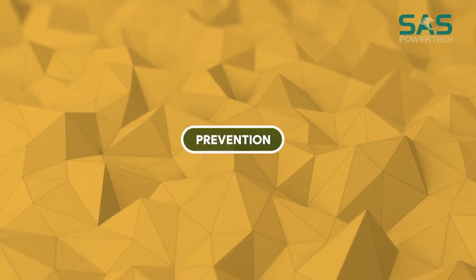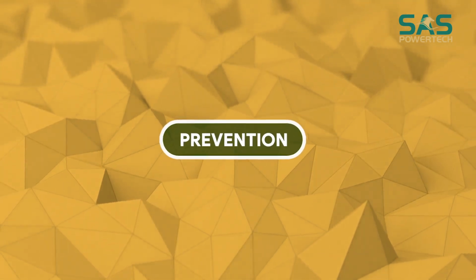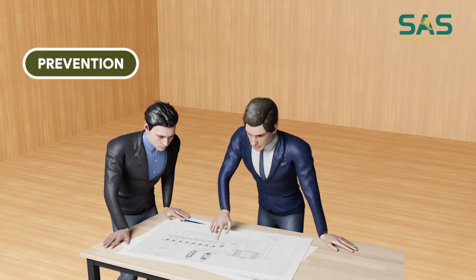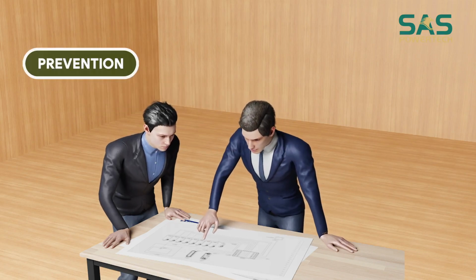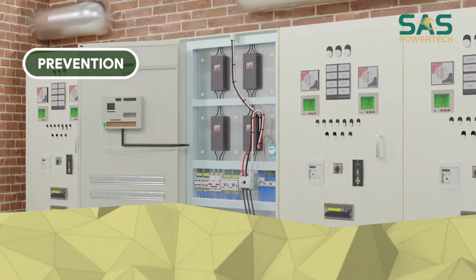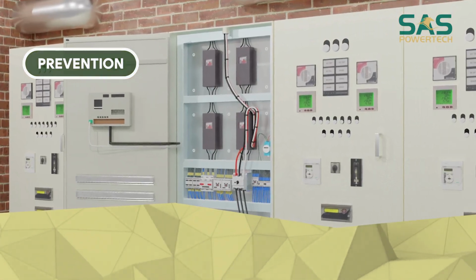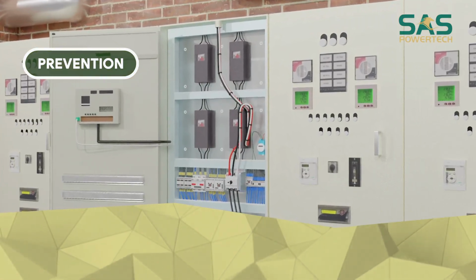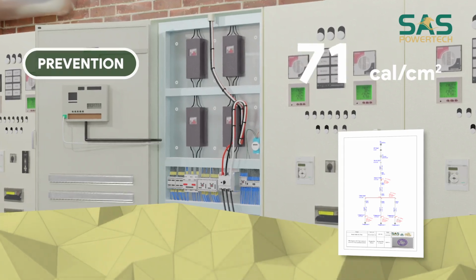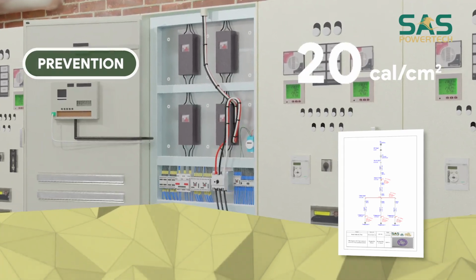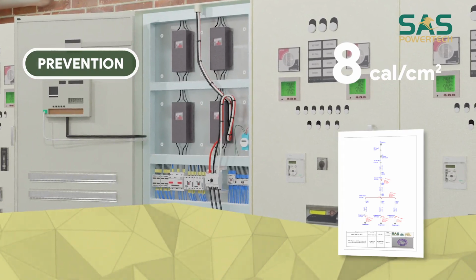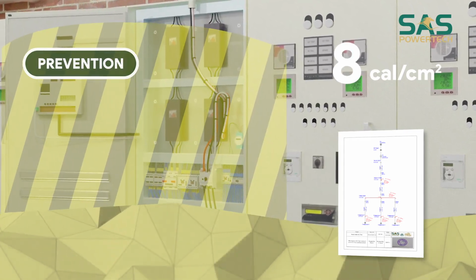Second, prevention. Mitigating steps can be taken to prevent an incident from occurring by designing it out, eliminating it, or removing a hazard at its source. With arc flash, completely eliminating the risk is very difficult in practice. This means trying to reduce the incident energy released by an arc flash or keeping personnel at a safe distance from the equipment.